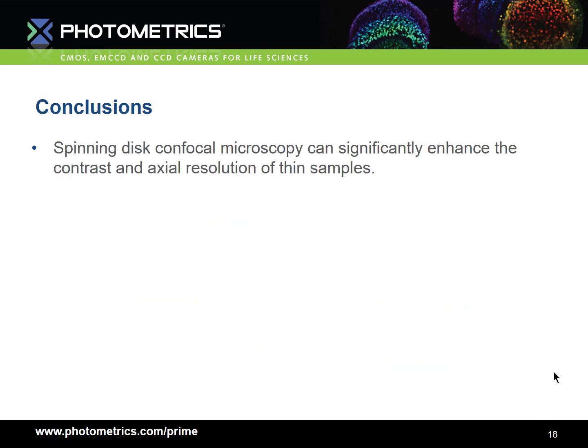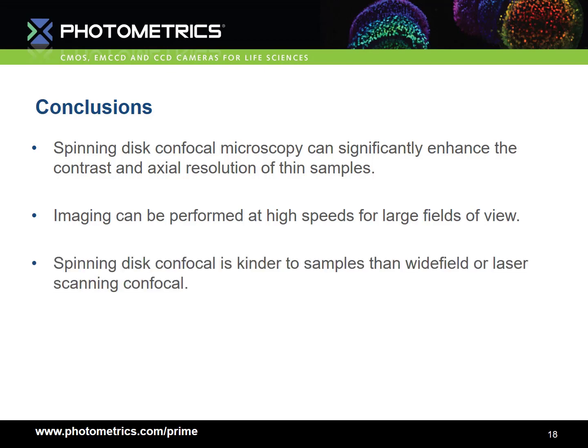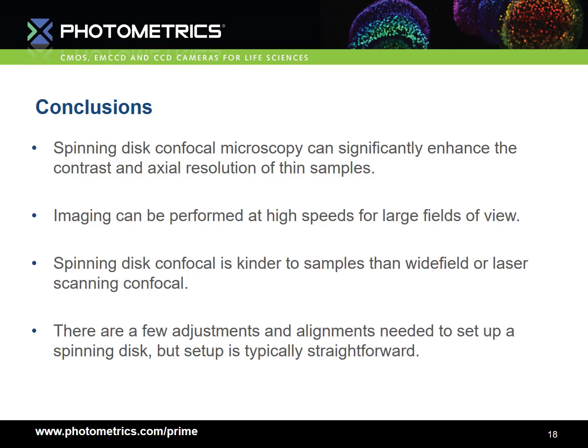In conclusion, spinning disk confocal microscopy can significantly enhance the contrast and axial resolution of thin samples. This is achieved by blocking the out-of-focus light from other planes other than the one that we're interested in. Imaging can be performed at high speeds with large fields of view, and spinning disk confocal is much kinder to samples than wide-field or laser scanning confocal, meaning photobleaching and phototoxicity are much reduced. There are a few adjustments and alignments needed to set up a spinning disk microscope in the optimal way, but set up is typically straightforward.